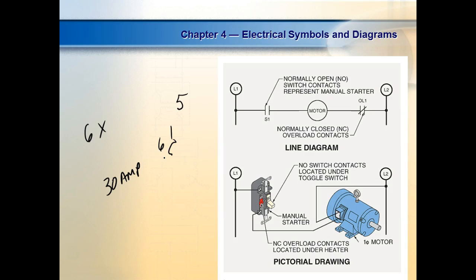It lets the motor start. It's just that if it draws that over current over a certain amount of time, it will do what? It'll trip the motor out. We call these overloads. Some of your small motors, the overloads are built inside the motor. And they're usually thermal, guys. And they usually reset automatically.